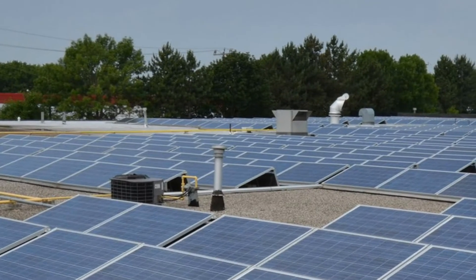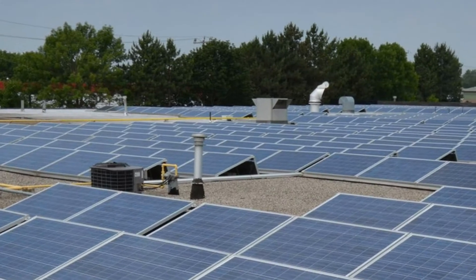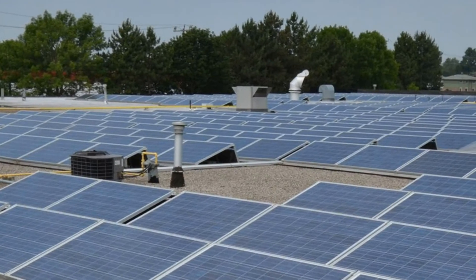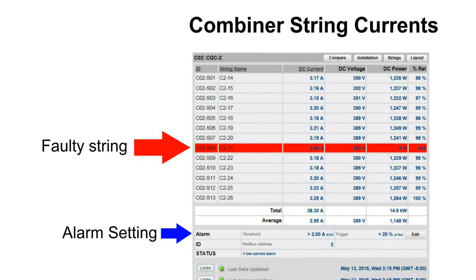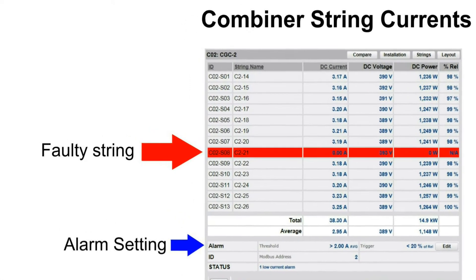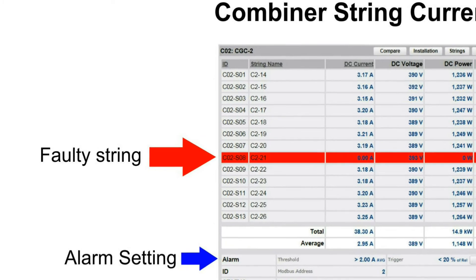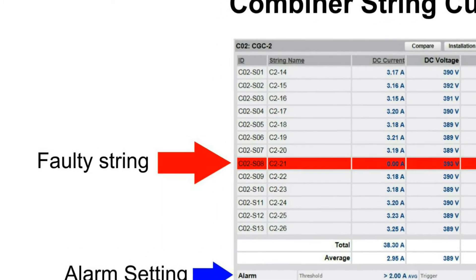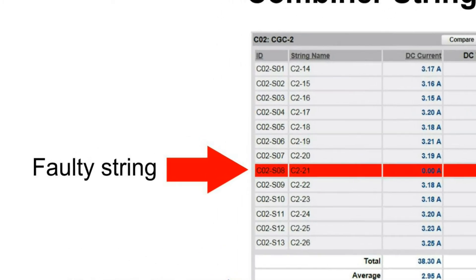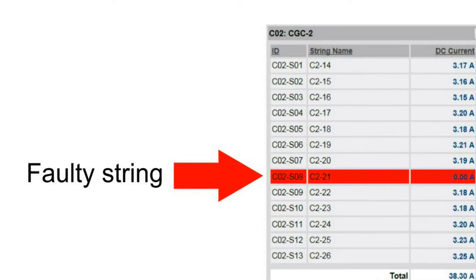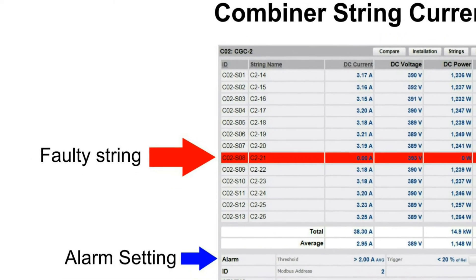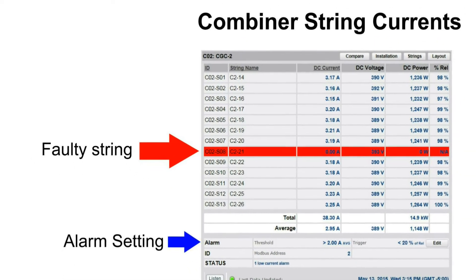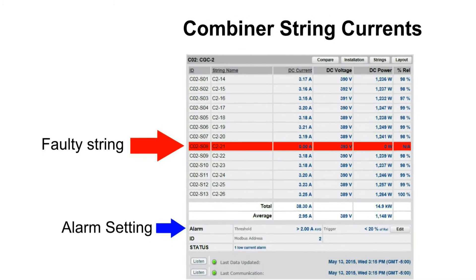This solar PV generation system has over 1100 panels connected to 13 combiner boxes. Scroll down this screen to see the output current, voltage and power of every string. Combiner box 2 is showing an alarm condition highlighted in red because string 8 has no output current. Although SolarView monitors the system 24-7, it is set to wait several hours before sending an alert to prevent nuisance alarms during startup or for short-term variations.